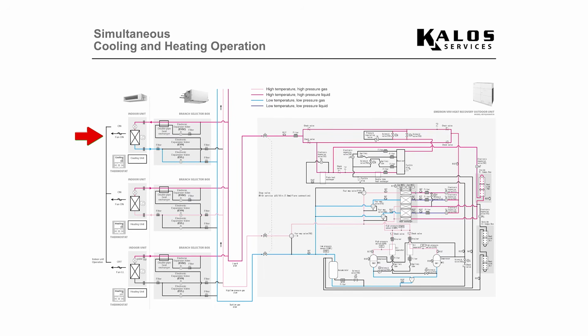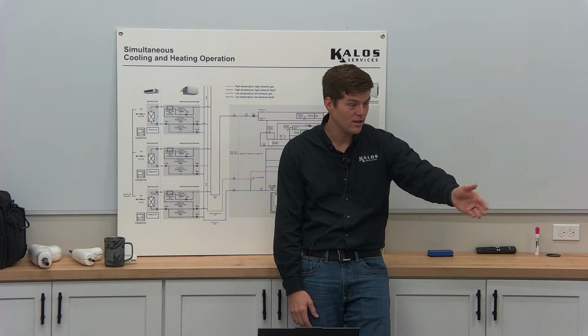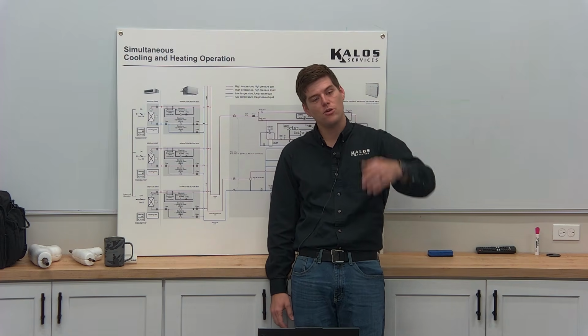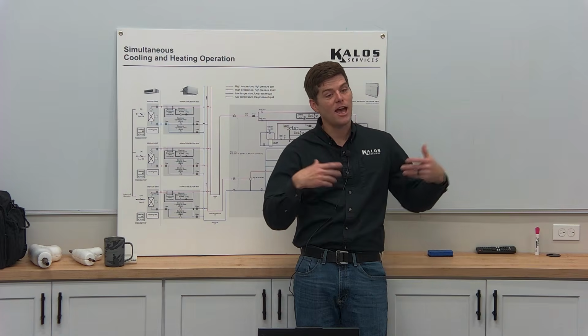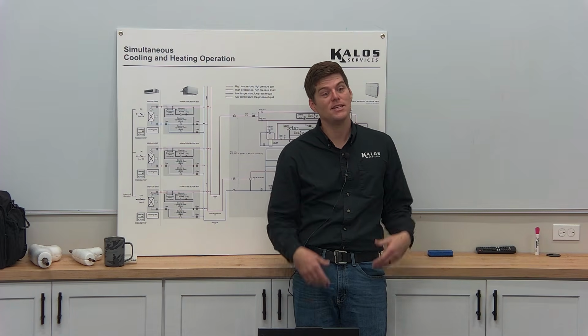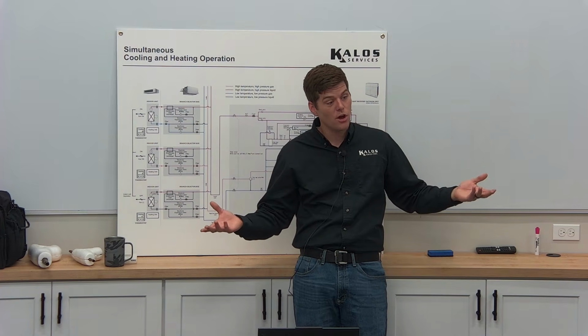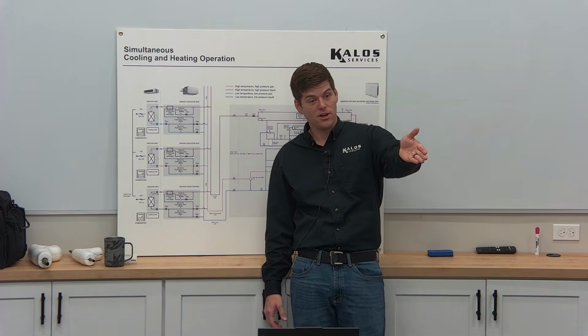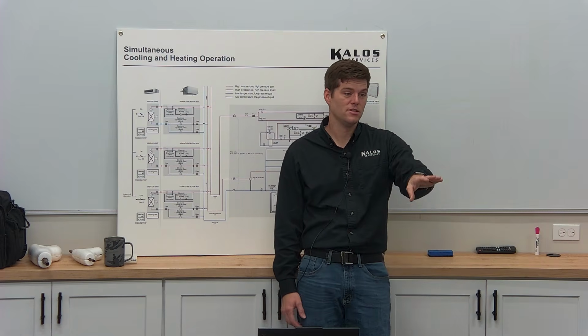And before we get into this particular diagram here, the main premise behind this is just this outdoor unit, its only job is to make sure its customers are happy, right? This one, this one, this one. Depending upon how many you connect to it, the only job it has is to deliver refrigerant. That's it. And that's all it cares about. It says that you need cooling. It says you need cooling. You're satisfied. You need cooling. Okay, let me see how many that is. Let me see how far off of set point those thermostats are. Let me see how big of a unit it is. These outdoor units know that you're a 1 ton, you're a 6 ton, and you're a 2 ton. No offense to 6 ton.